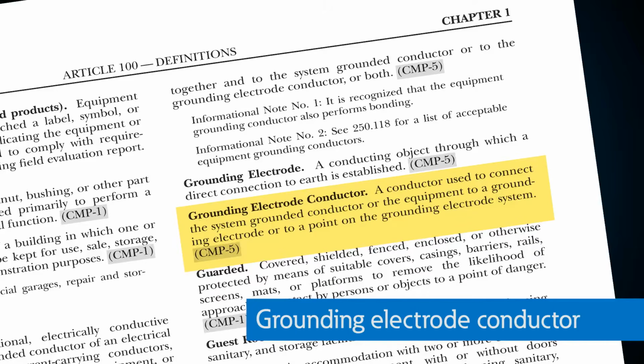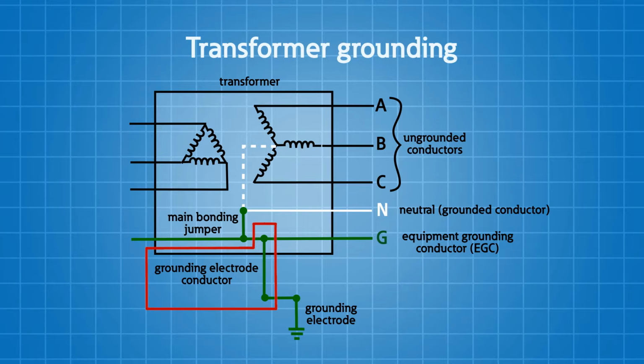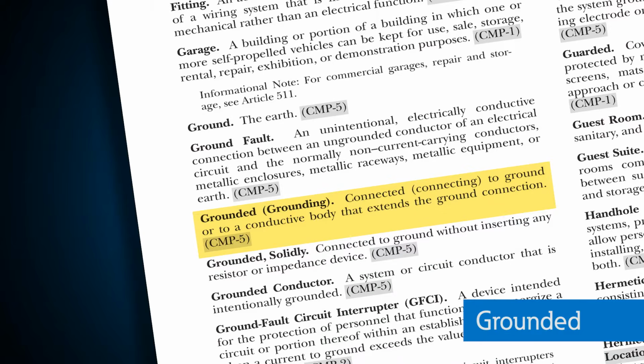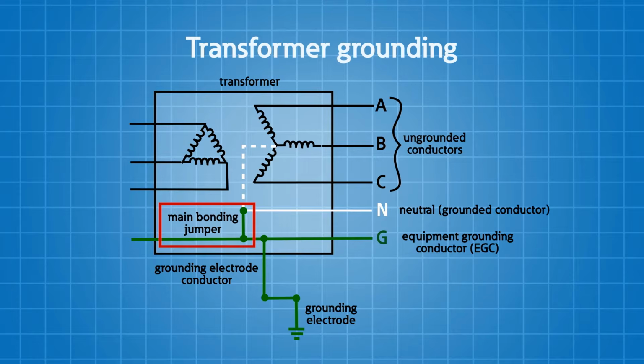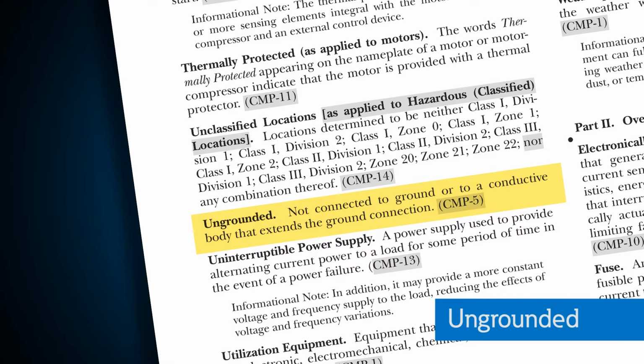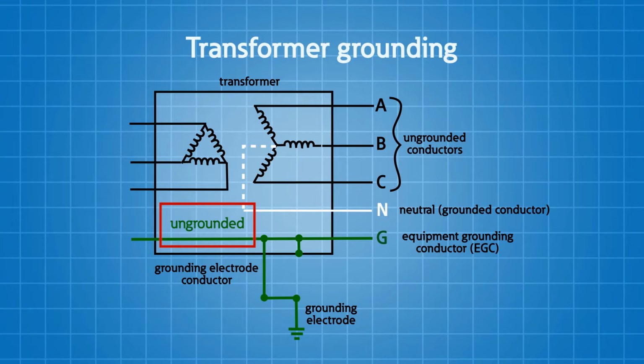Now let's talk about the grounding electrode conductor. This is the conductor used to connect the system neutral conductor or grounded phase conductor or the equipment to the grounding electrode system. When we use the term grounded, this is when we say we are connected to the earth or to some body that extends that earth connection. Ungrounded is just the opposite, right? It's not connected to ground or to a conductive body that extends that ground connection.